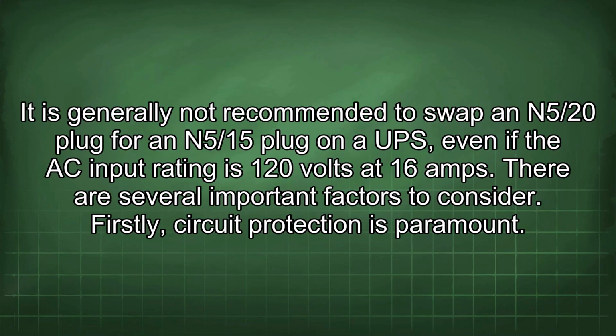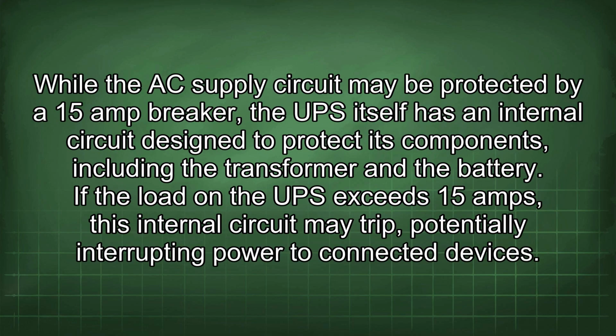It is generally not recommended to swap an N5/20 plug for an N5/15 plug on a UPS, even if the AC input rating is 120 volts at 16 amps. There are several important factors to consider. Firstly, circuit protection is paramount. While the AC supply circuit may be protected by a 15 amp breaker, the UPS itself has an internal circuit designed to protect its components, including the transformer and the battery. If the load in the UPS exceeds 15 amps, this internal circuit may trip, potentially interrupting power to connected devices.